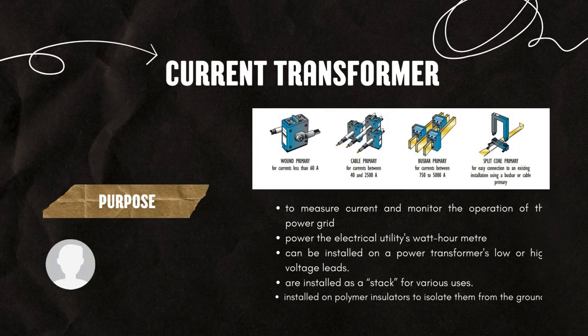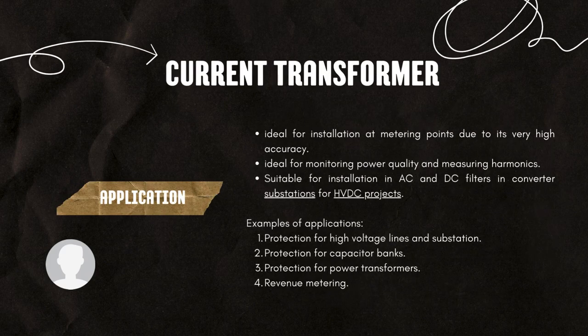CTs are widely used to measure current and monitor the operation of the power grid. They also power the electrical utilities for metering. CTs can be installed on a power transformer at the high voltage side, installed as a standalone unit for various users, and installed on polymer insulators to insulate them from the ground. Applications include protection for high voltage lines and substations, protection for capacitor banks, protection for power transformers, and revenue metering.